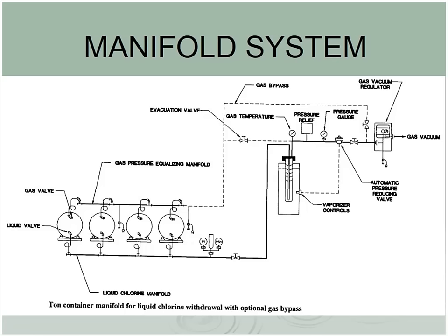Any idea why? Just evaporates in the air? The liquid will spill to clean up and the gas just vanishes? That's not it. When the liquid evaporates, it generates 479 times the volume, whereas the gas just comes out as gas. You don't want to fill up the room too fast.